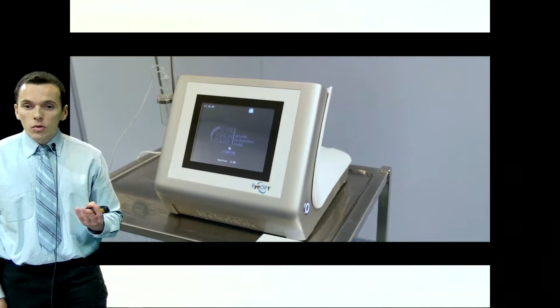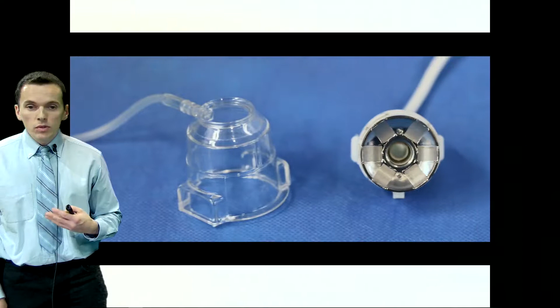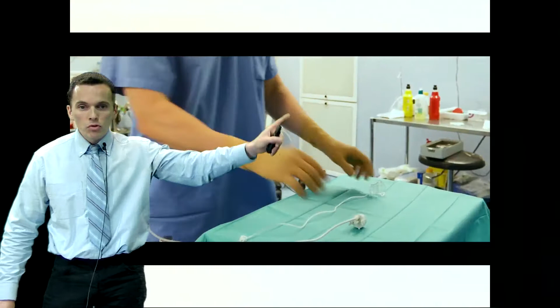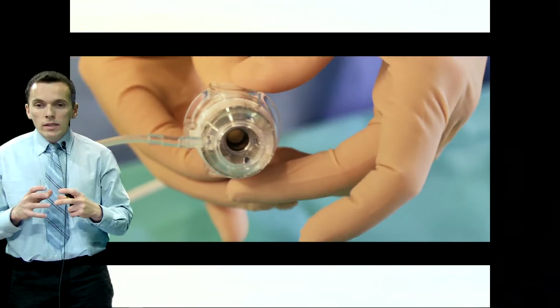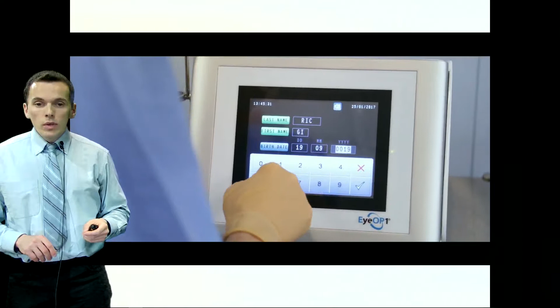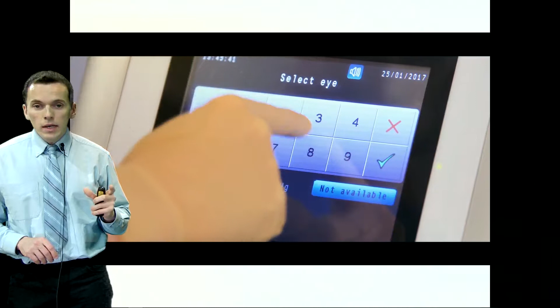So we can see one patient that I'm going to treat. We can see the machine that we use to set the parameters of the treatment. We can see the probe with 6 piezoceramic transducers, and a cone designed to be put against the eye. We insert the probe into the cone against the eye, and then we treat the patient. Before beginning, we set the parameters of the treatment, and we can choose the number of sectors to be activated, 6 or 8. For example, in this given patient, I'm going to treat with 6 sectors activated.